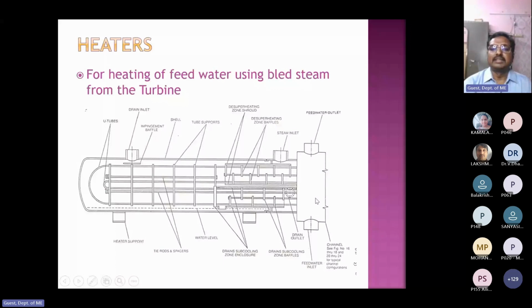In this heater, this is the steam inlet. Steam from the turbine enters the heater, and the steam falls directly over the tubes, and this entire surface is filled. After filling, it goes to the drain outlet. Actually, the drain is provided at the middle. So what happens here? We take low pressure steam from the turbine through the extraction. Once heat energy is removed from the steam, it will condense directly. The steam will condense, and that condensate is removed and goes to the condenser again.